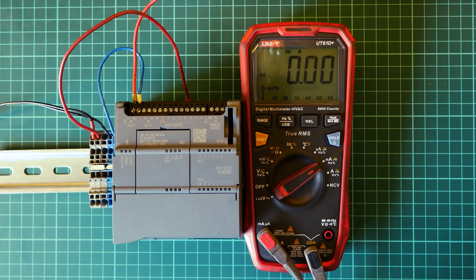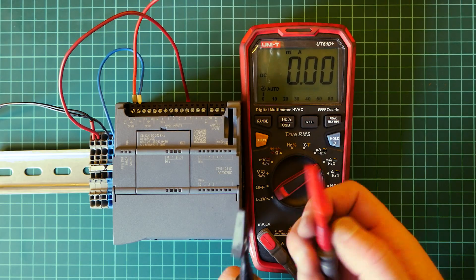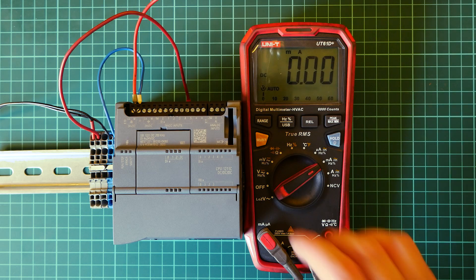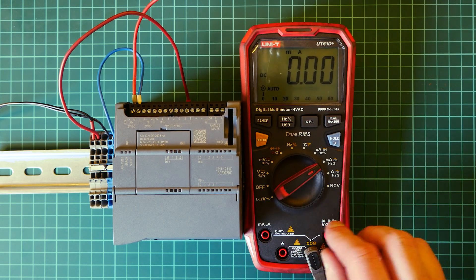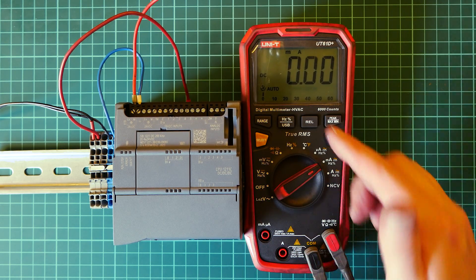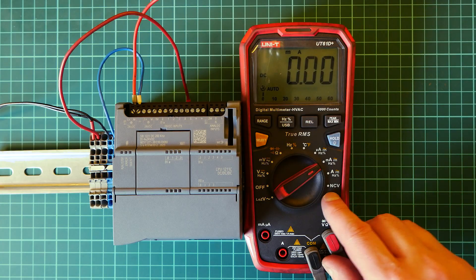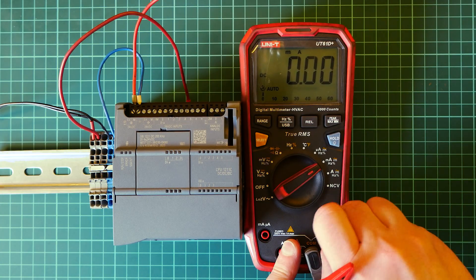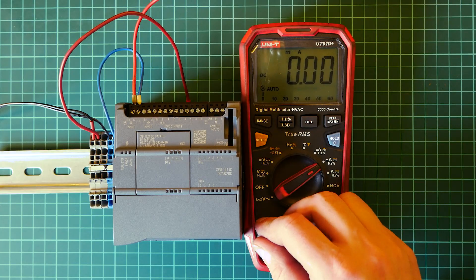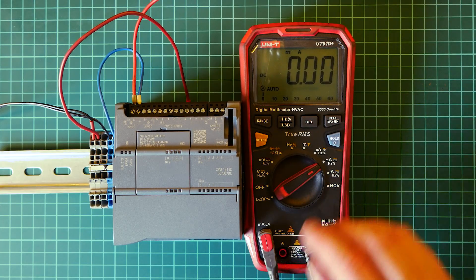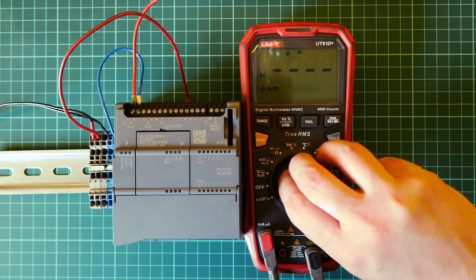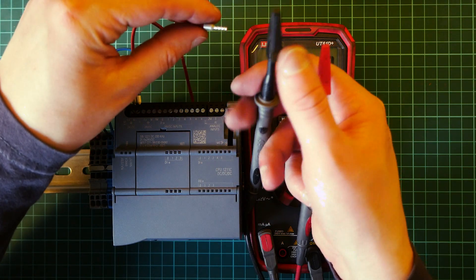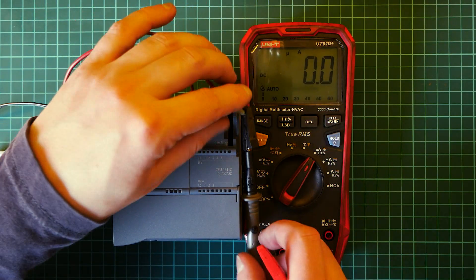Now I want to measure how much current is required for this PLC. To power it we need 24 volts DC. I just want to see how much current it takes. Now there is no security when the probe is in voltage mode. There is no fail safe. But actually it's normal, not actually an issue.